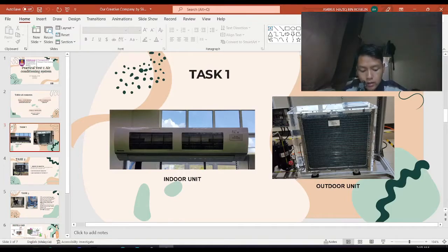Step by step, first of all, we need to wear our safety gear, which are masks, glasses, and gloves. First, we need to clean the cooling coil, condenser, air filter, evaporator, cleaning the blower fan and exhaust fan, and check the thermostat condition, replace if necessary.